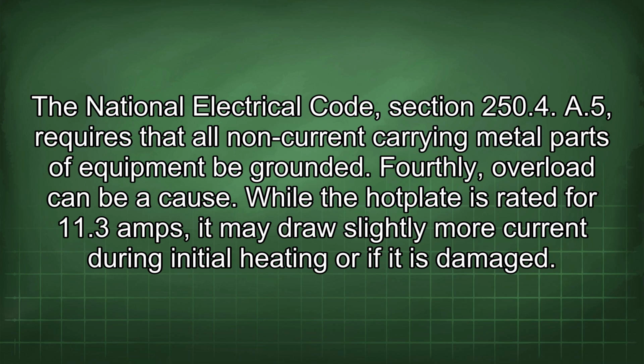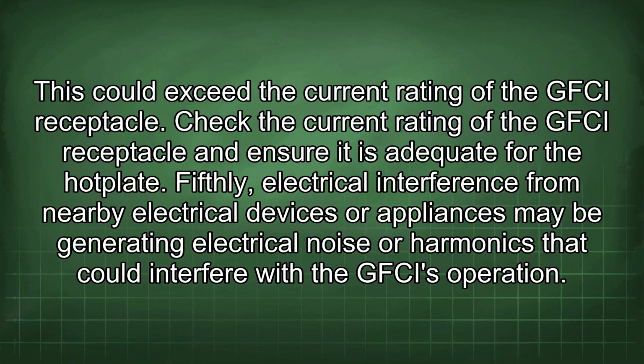Fourthly, overload can be a cause. While the hot plate is rated for 11.3 amps, it may draw slightly more current during initial heating or if it is damaged. This could exceed the current rating of the GFCI receptacle. Check the current rating of the GFCI receptacle and ensure it is adequate for the hot plate.